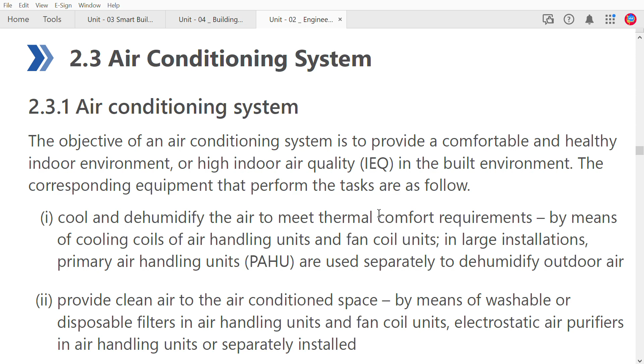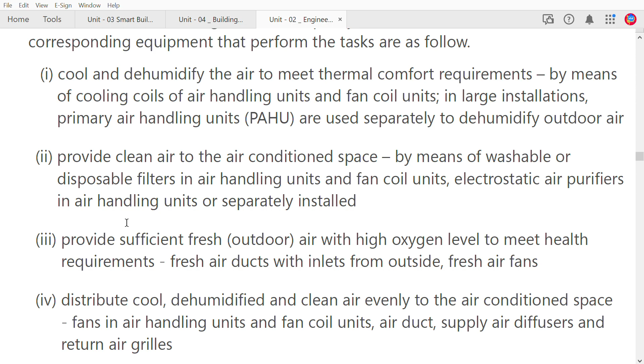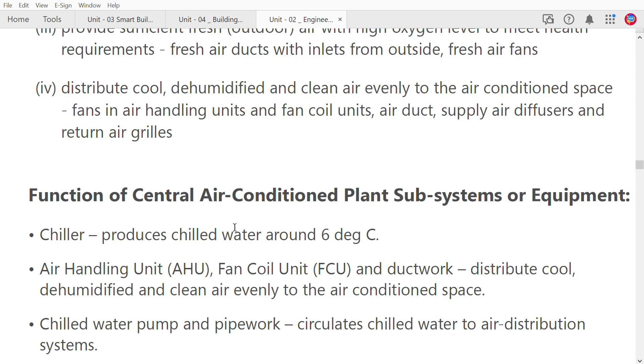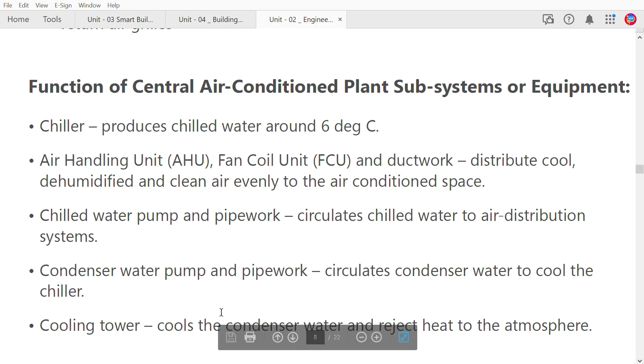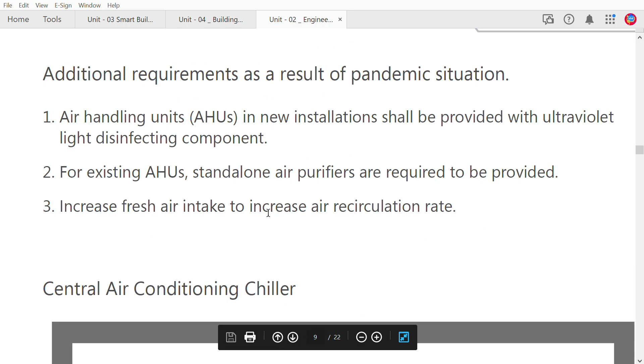So the air conditioning system's objective is to provide comfortable and healthy indoor air so that the air quality in the built environment corresponds to the equipment. Cool and dehumidified air is a thermal comfort requirement by means of a cooling coil and air handling unit. In a large installation, primary air handling units treat and dehumidify outdoor air. It also provides clean air, sufficient fresh and distributed cool dehumidified air. The function of centralized cooling systems, with equipment like chillers, air handling units, chilled water pumps, condenser water pumps and piping, and cooling tower, is to cool down the water and then reject heat to the atmosphere. So this is the centralized air conditioning system.